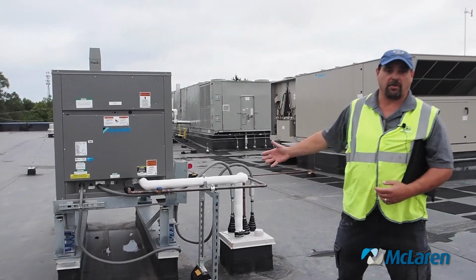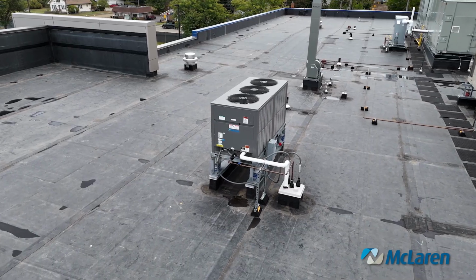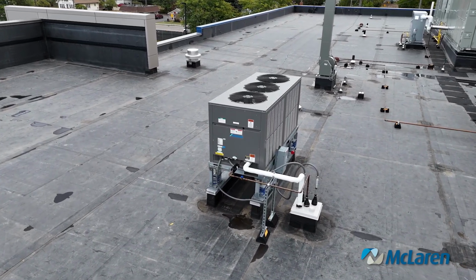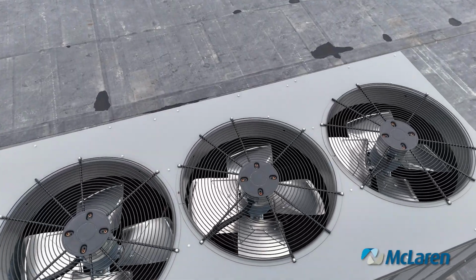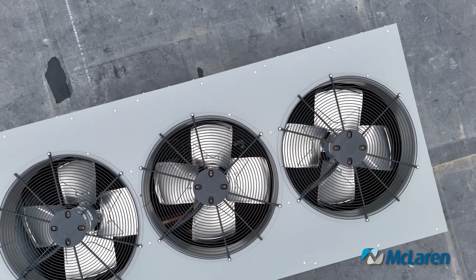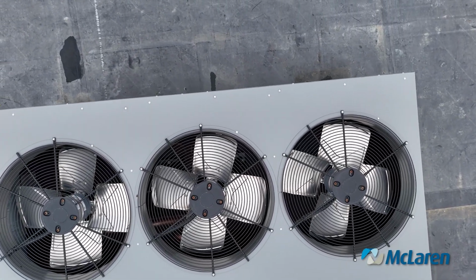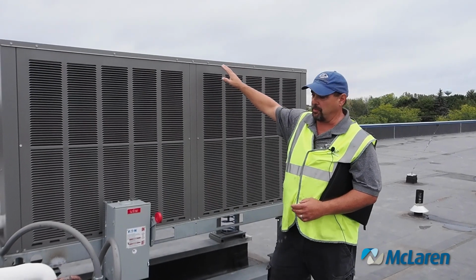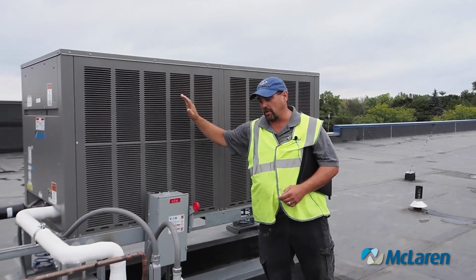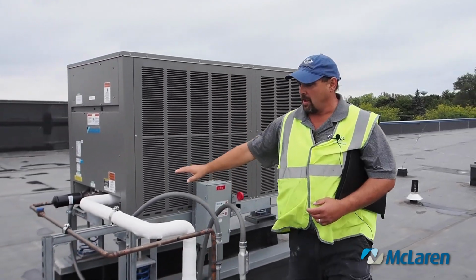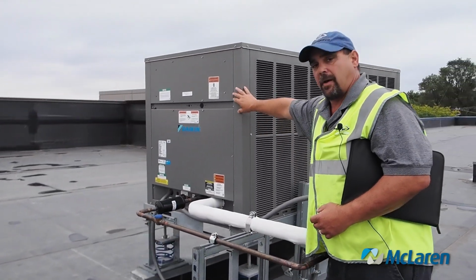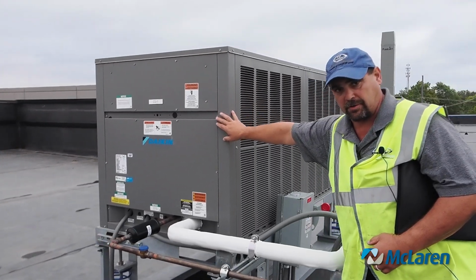This is another condenser. Inside of here is a compressor section and the condenser section, and it also has condenser fans on top. These condenser fans require zero maintenance as well. If they go bad, you just replace them. At least once a year, you lock out, tag out. Over here, you take off the top cover panel and you would check all your electrical connections.